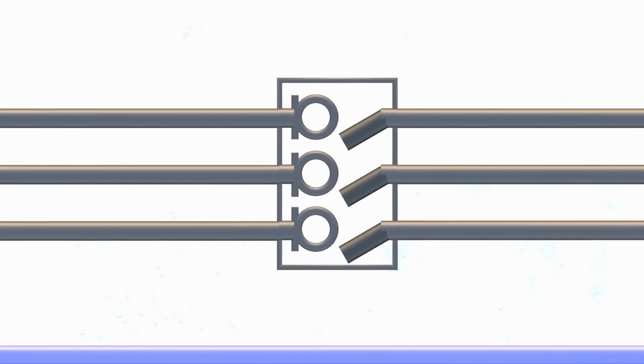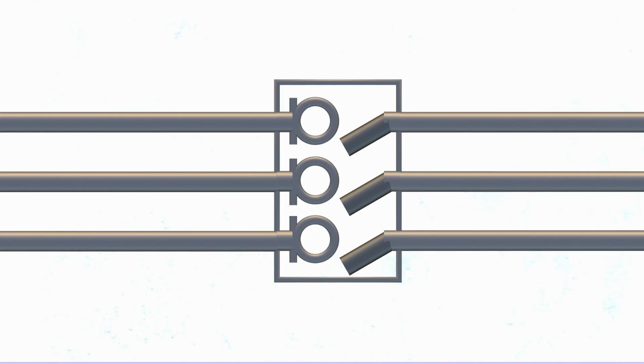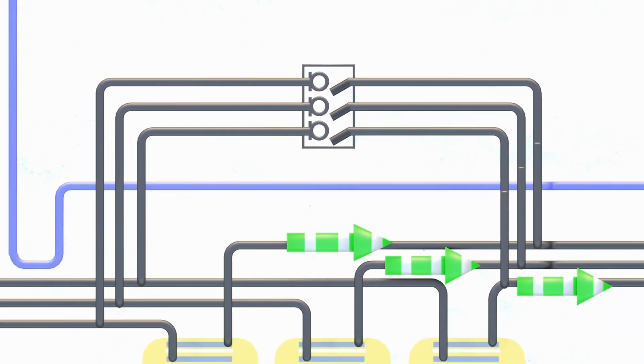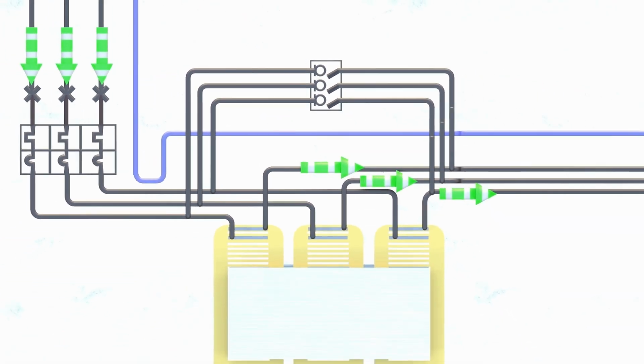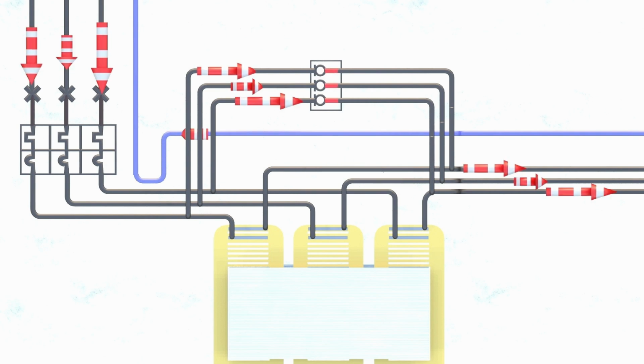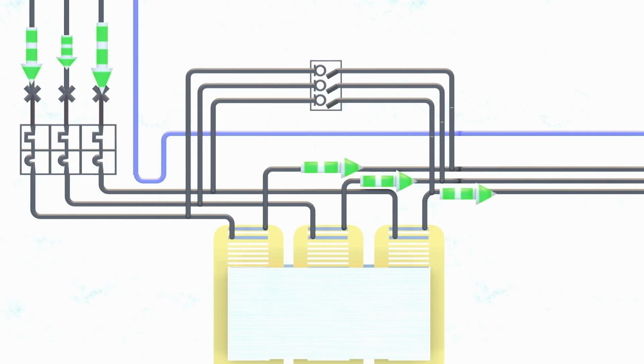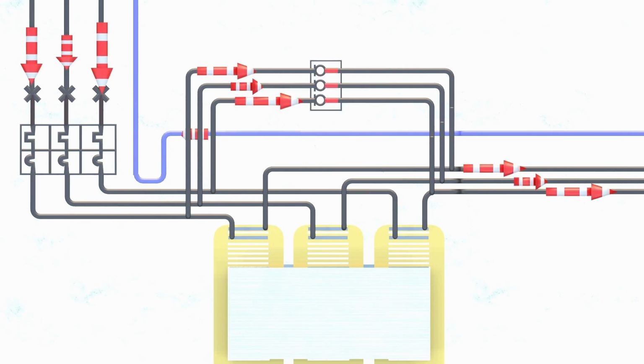For the validated ECV measurement method, an automated and remote-controlled bypass system was developed in collaboration with the manufacturer of the circuit breaker. The bypass switch can be switched between saving and bypass operation every 300 seconds, with a current of up to 4,000 amperes. The asymmetrical leakage currents and the heightened neutral currents in bypass mode can be clearly seen and easily observed. The current flows in green in saving mode.